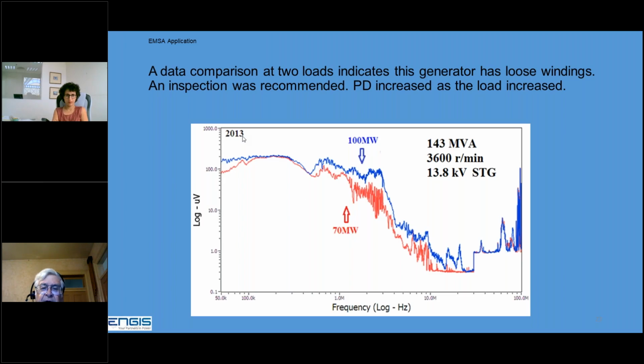And this is 2013 data on this 143 MVA generator. At 70 megawatts, we get this curve, the red one. At 100, we get higher readings. The windings are loose. They're vibrating more at 100 megawatts. So again, they need to schedule an outage, pull the rotor, and probably re-wedge, reblock, and tie the end windings.